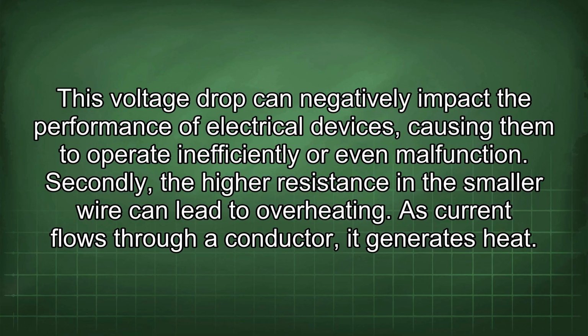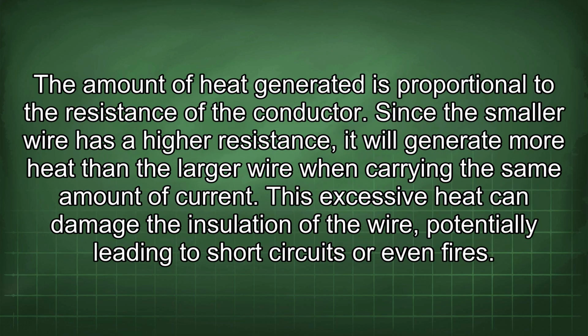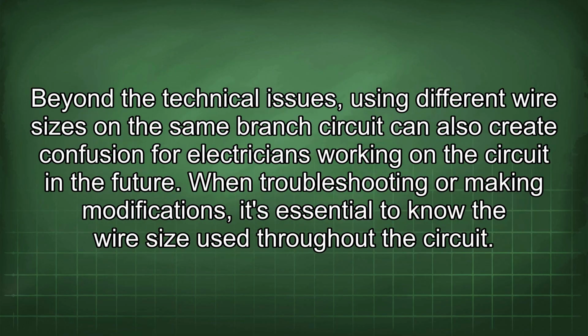Secondly, the higher resistance in the smaller wire can lead to overheating. As current flows through a conductor, it generates heat. The amount of heat generated is proportional to the resistance of the conductor. Since the smaller wire has a higher resistance, it will generate more heat than the larger wire when carrying the same amount of current. This excessive heat can damage the insulation of the wire, potentially leading to short circuits or even fires.